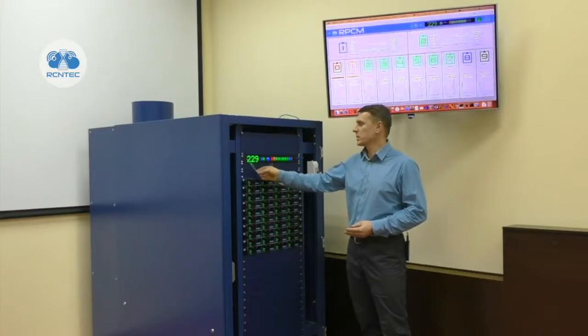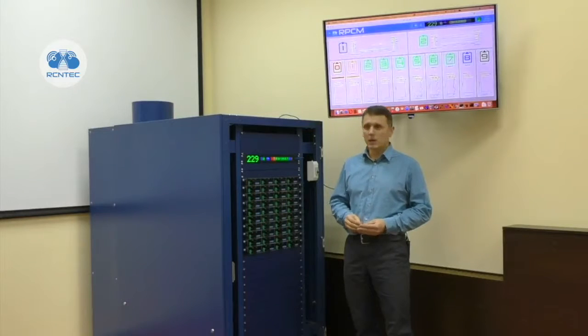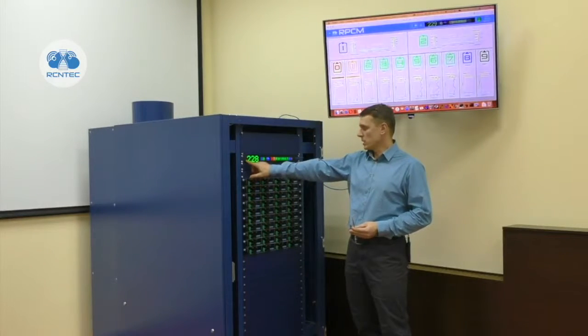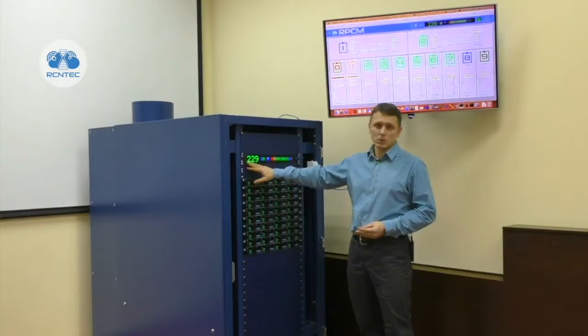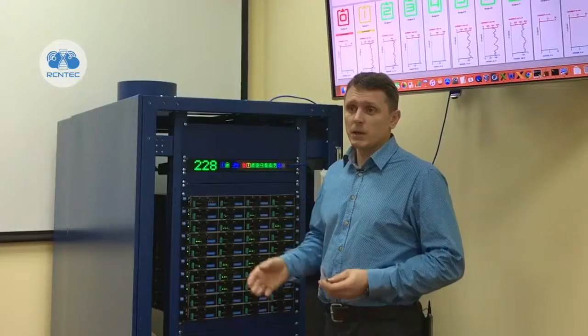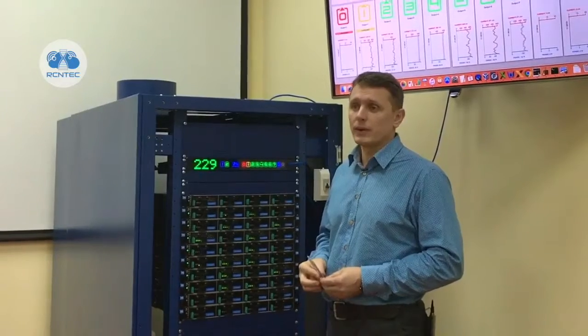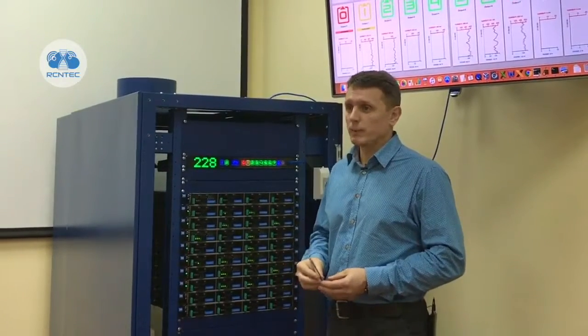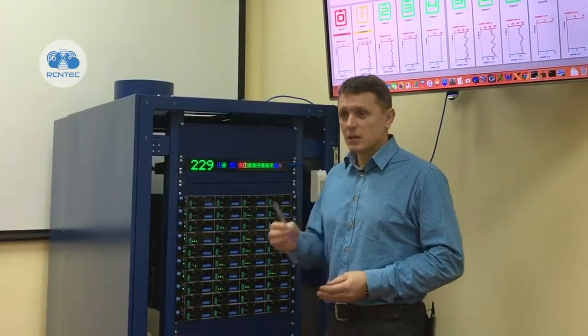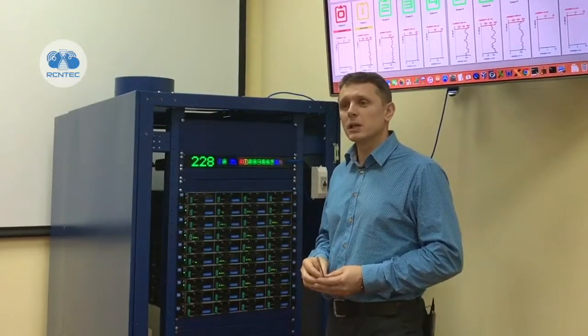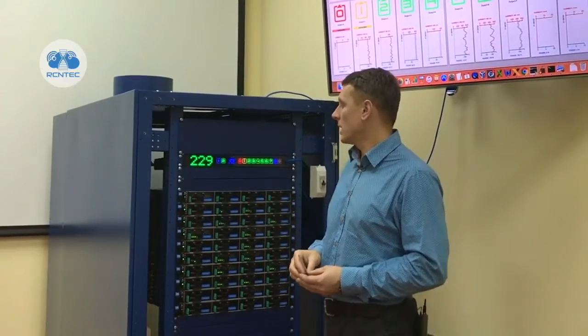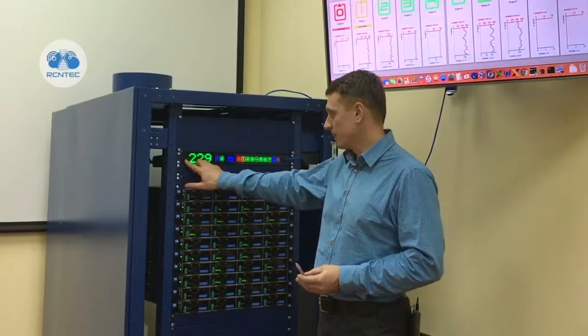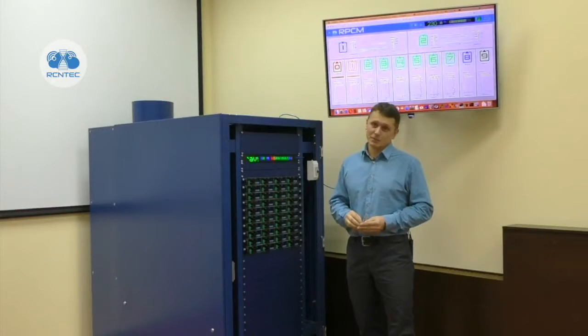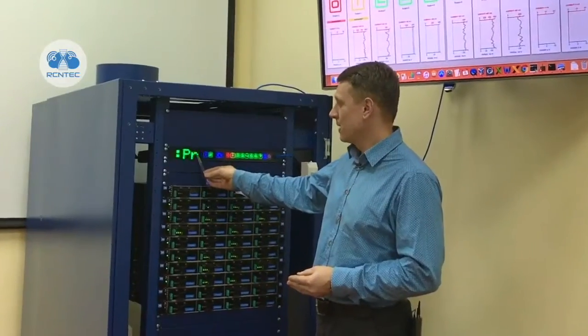Now, the display shows instant voltage value. By switching the display mode, you can get additional information such as total load in amps or kilowatts, IP address, MAC address, serial number or serial name. Yes, you heard it right. All our devices have unique serial names. For instance, this module's name is Right Eye.